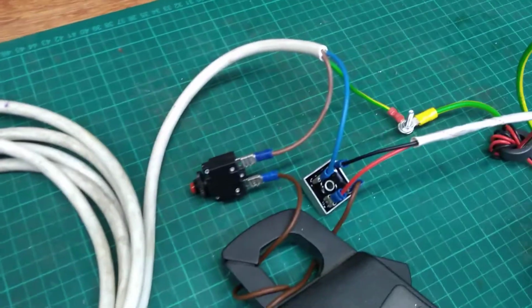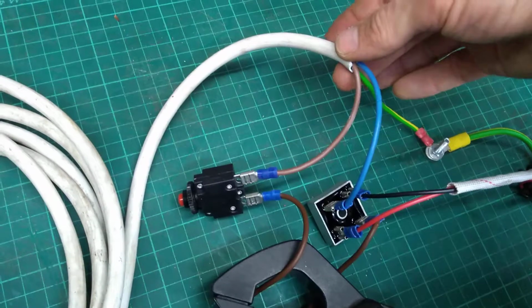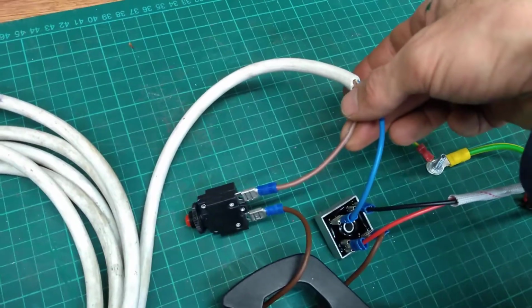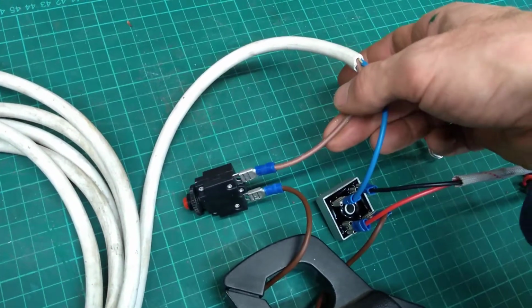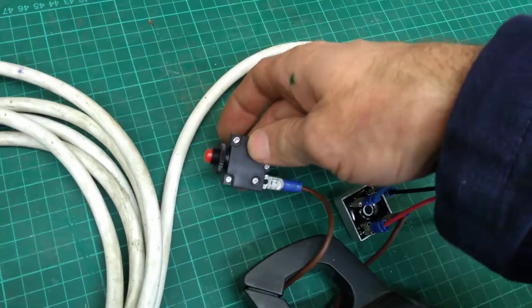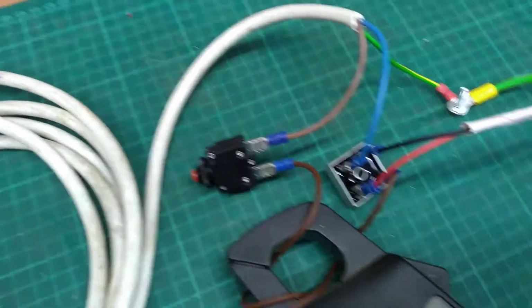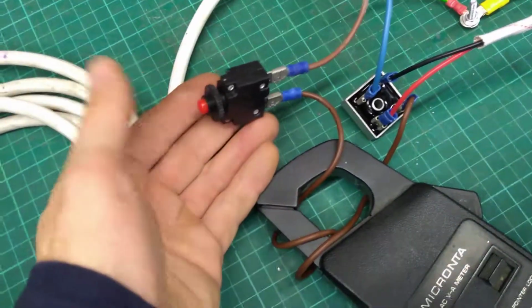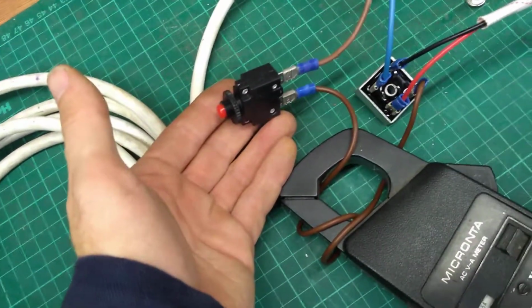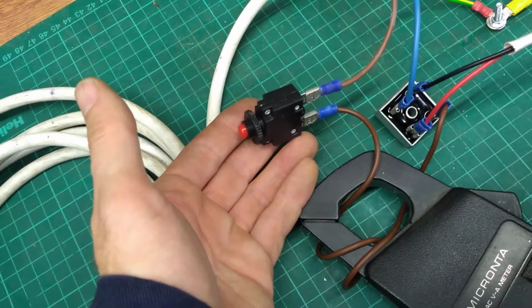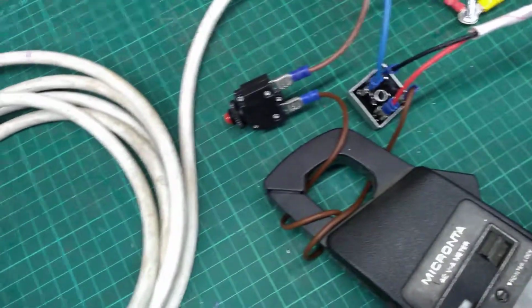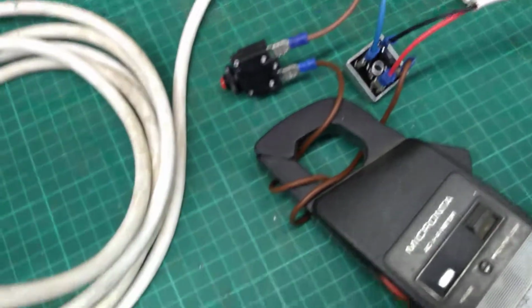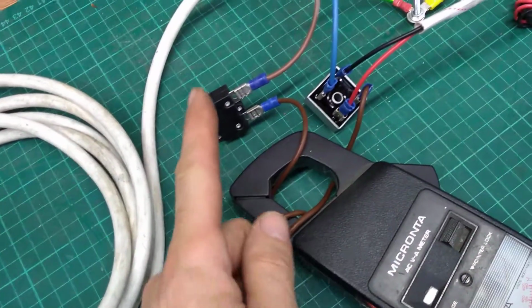Okay, so let's have a quick look in a little bit more detail at my setup. So I've got the live of the, let's call it 110 volts. The live of the 110 volts goes through this thermal overload. It's a 6 amp rated thermal overload, so it will continuously supply 6 amps, but if you try to draw more than 6 amps on a longer basis, it will trip. So for example, if this motor were to stall, or if I were to do something silly with the configuration of this, hopefully that's going to trip out. Okay, so that's the first thing.